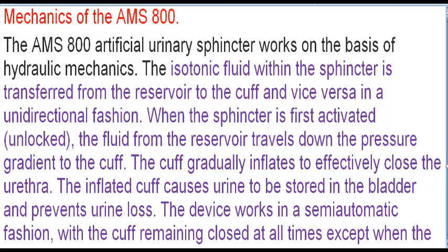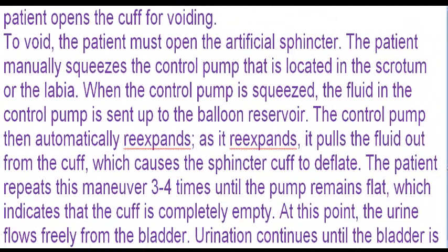The device works in a semi-automatic fashion, with the cuff remaining closed at all times except when the patient opens the cuff for voiding. To void, the patient must open the artificial sphincter. The patient manually squeezes the control pump that is located in the scrotum or the labia. When the control pump is squeezed, the fluid in the control pump is sent up to the balloon reservoir.